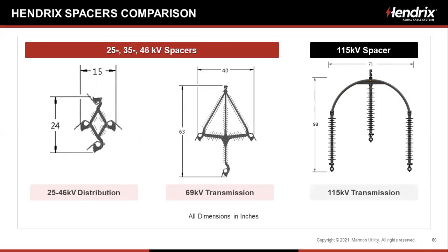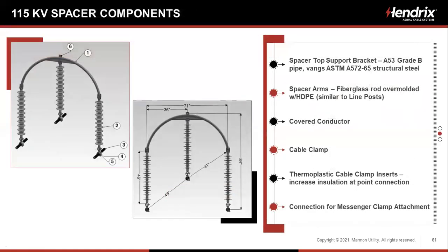Let's take a look quickly at the spacer here. The spacer is really different when we go to 115 kV. So this is not drawn to scale, and I apologize for that. But the 25, 35, 46 kV spacer, I didn't show the 15 kV spacer here, but the 25, 35, and 46 kV spacer, you can see that's 24 inches high. When we go to the 69 kV spacer, now it's a full 63 inches. When we go into the 115 kV spacer, it's 3.5, 4 times the size of that 46 kV spacer. So it's starting to get a little bit large. We also had some mechanical issues. So, when you get a spacer that large, you really can't mold a piece of polyethylene that big.